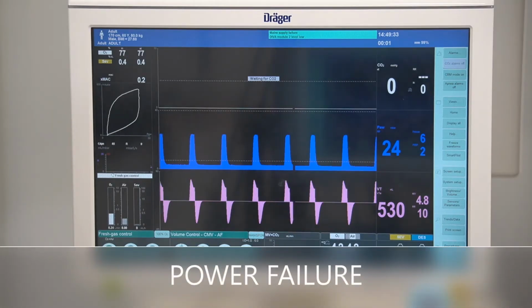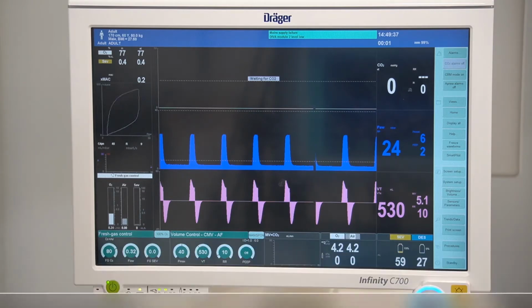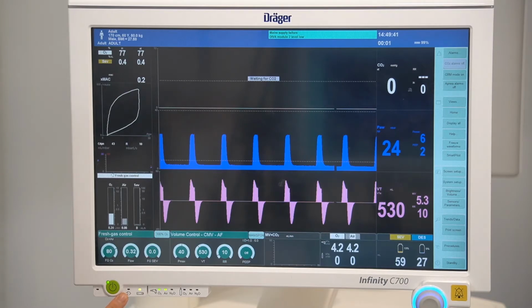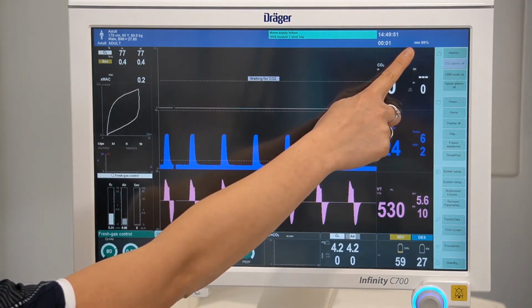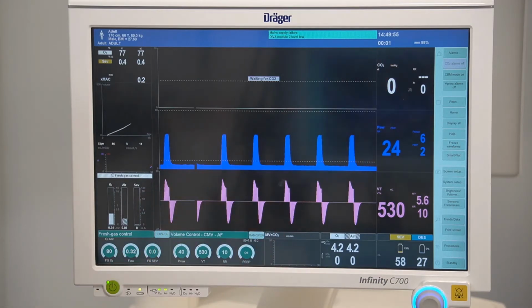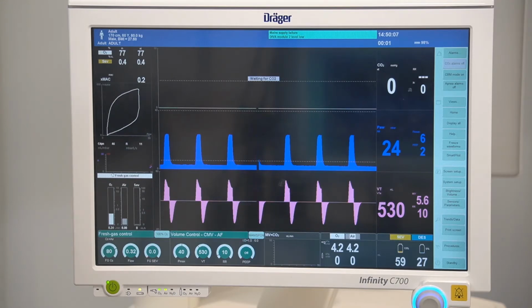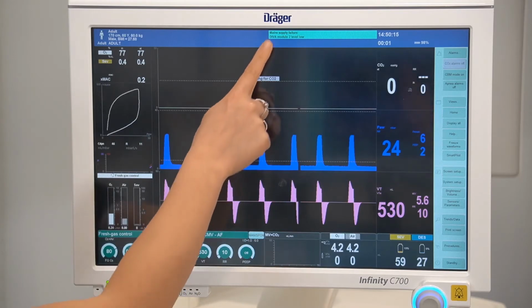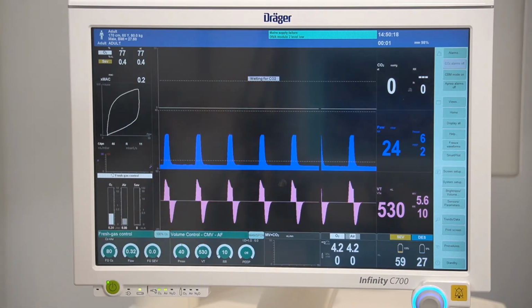In the event of a central power supply failure, the device will automatically switch over to the internal battery. You will no longer see an LED light indicator above the plug power symbol, and you will see the remaining internal battery capacity displayed in the top right-hand corner of the header bar. A fully charged internal battery will maintain operation for a minimum of 30 minutes and up to 90 minutes, depending on ventilation settings. Once the battery capacity reaches below 20%, the alarm priority will increase and become more prominent. The device requires 10 hours of charging for a completely flat battery. Manual ventilation and oxygen delivery is possible during complete power failure.